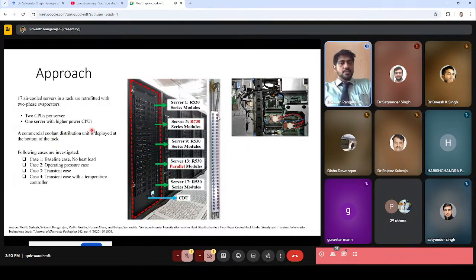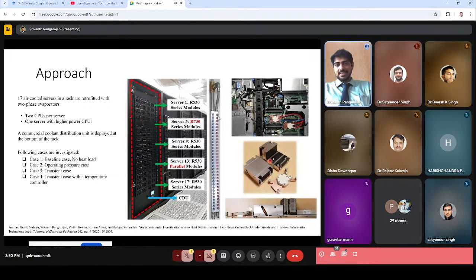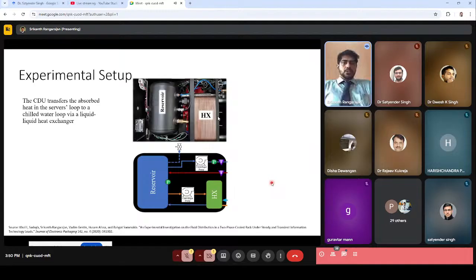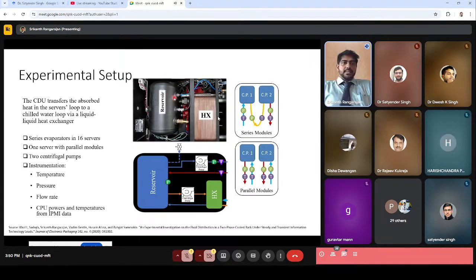So a commercial coolant distribution unit is deployed here, and this problem is much more complex because on each server you have this cold plate. The coolant distribution unit is sitting at the bottom, and it is trying to distribute the fluid to all of these servers. You can see that these air-cooled heat sinks were replaced with this liquid cold plate. So this is a schematic of the experiment setup. The coolant distribution unit transfers the absorbed heat in the server's loop to a chilled water loop via a liquid-liquid heat exchanger. And we had series evaporators in 16 servers and 1 server with parallel modules.